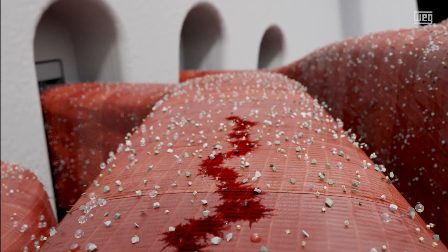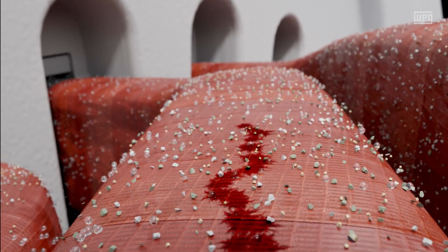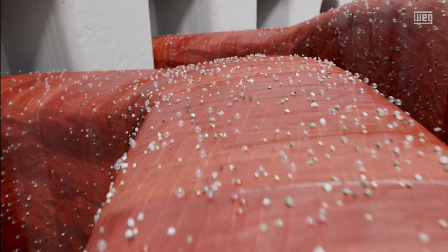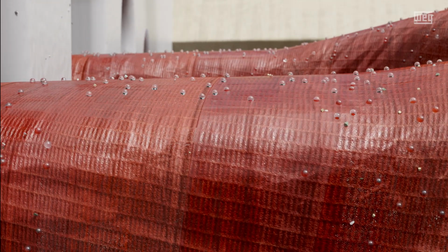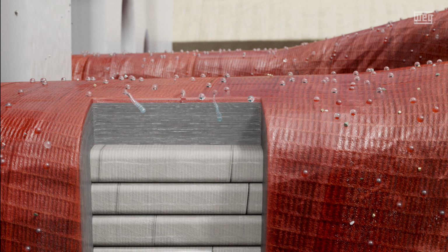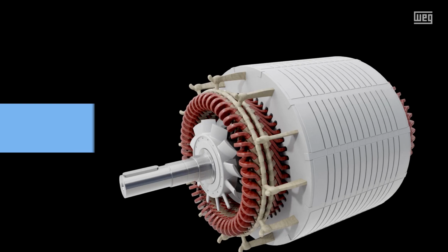The moisture can become an issue, especially on machines that can stay out of service for longer periods of time without proper prevention of water condensation on the winding. Even windings considered sealed can be affected in case of prolonged exposure to this condition of condensation.